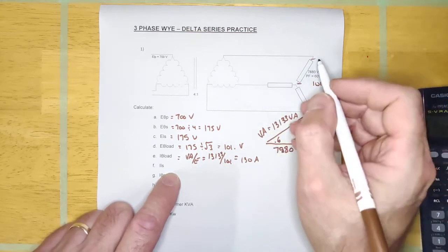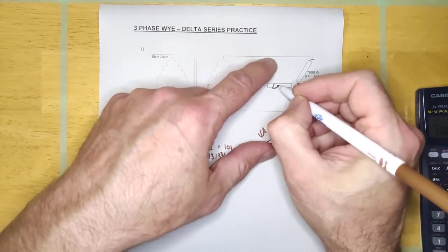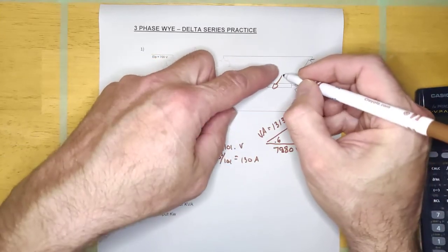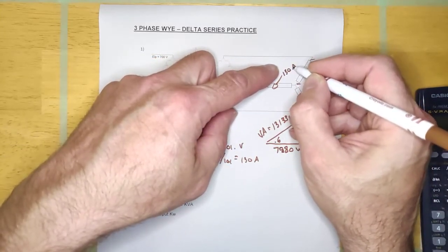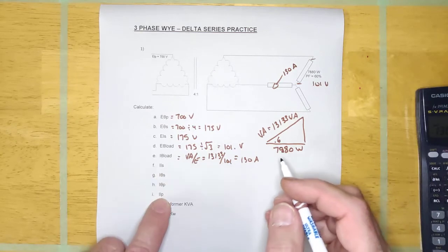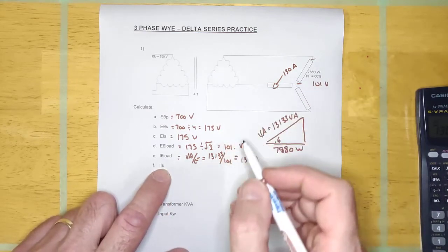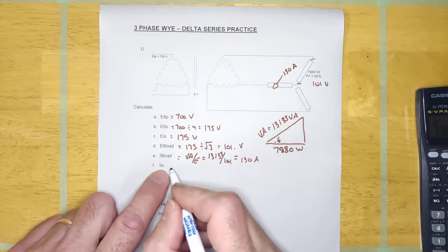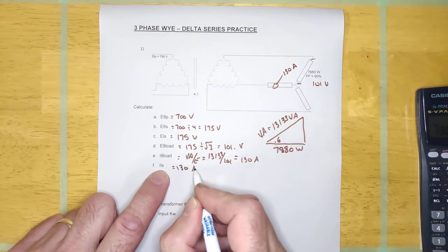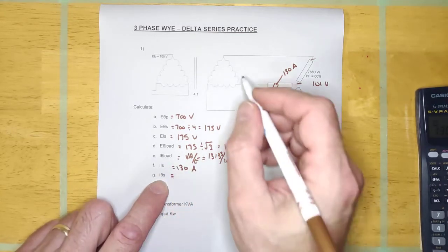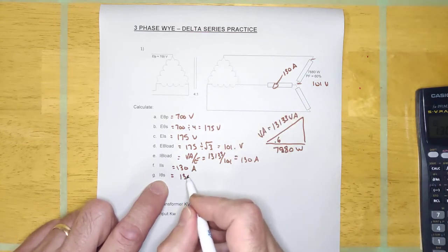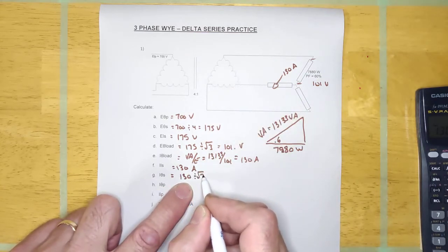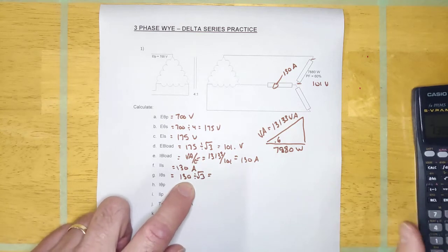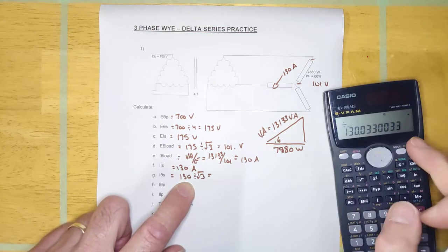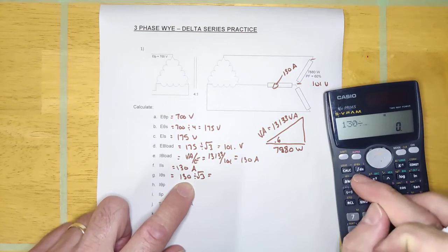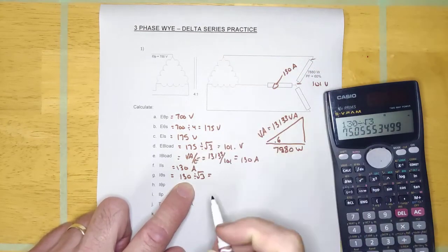130 amps, okay, and that would be, if I clamped onto any one particular load here, 130 amps right there. Now I'm going to take that current back. Looks like I-line secondary is also going to be 130, right guys? I-phase secondary looks like I'm going to divide it by root 3. So we'll do 130 divided by root 3, and that's because it's delta here.